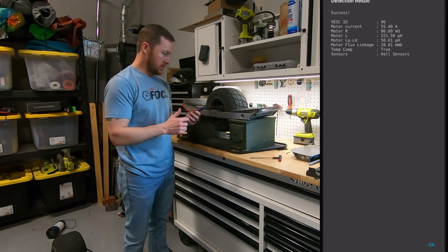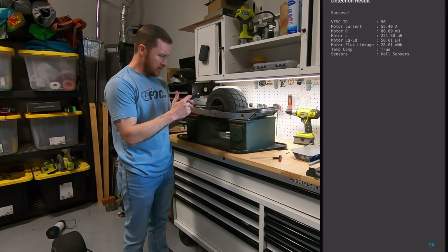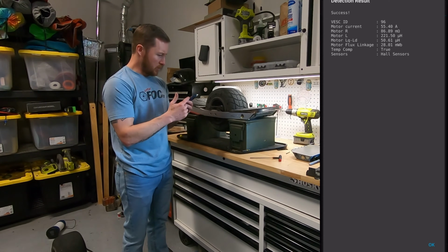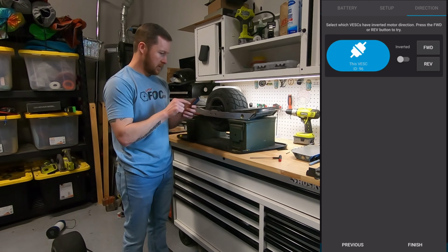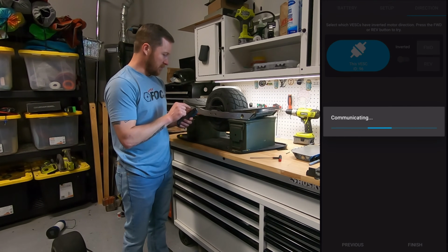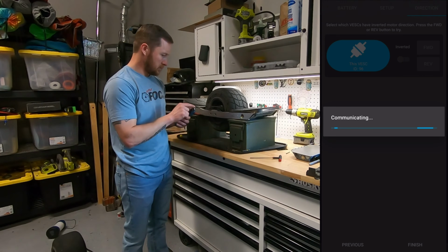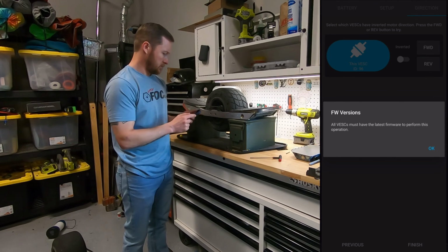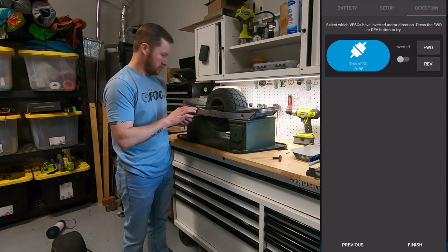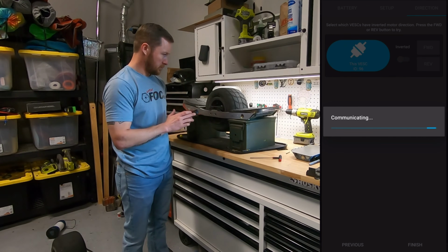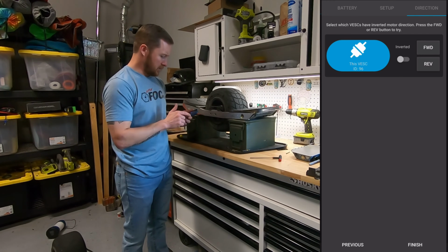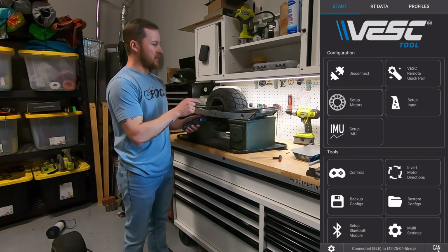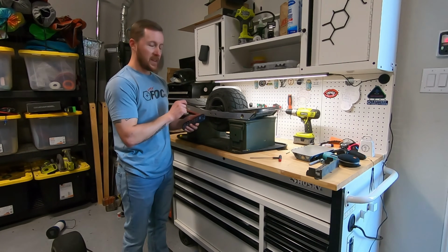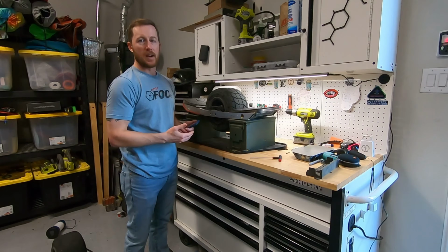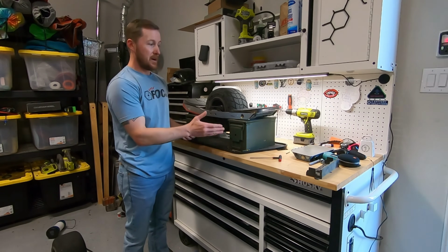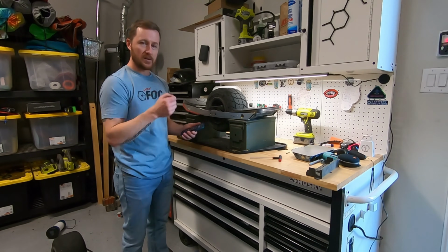Success. Very nice. Looking at those values, that's about normal. So I'm going to hit OK. Test the direction, I'll hit forward. So that's good, and hit finish. If I hit forward and it turns backward, you'll hit that switch for invert motor direction, and you'll verify now it goes forward when I say forward, and you'll save it from there.